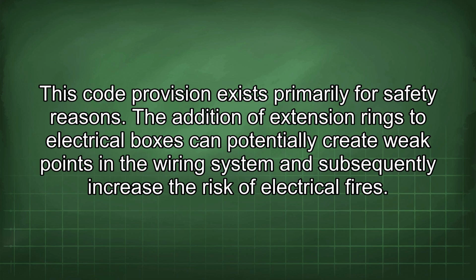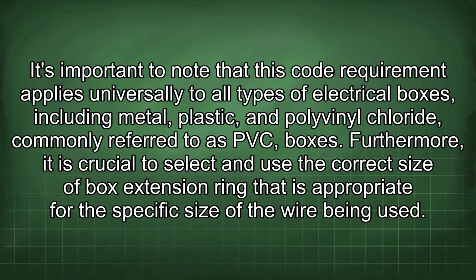The addition of extension rings to electrical boxes can potentially create weak points in the wiring system and subsequently increase the risk of electrical fires. It's important to note that this code requirement applies universally to all types of electrical boxes, including metal, plastic, and polyvinyl chloride, commonly referred to as PVC boxes.